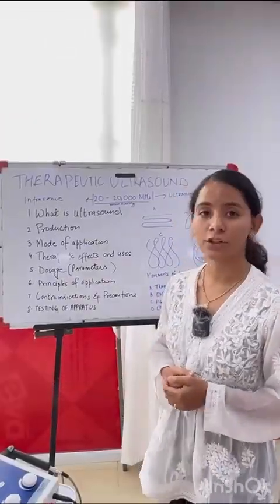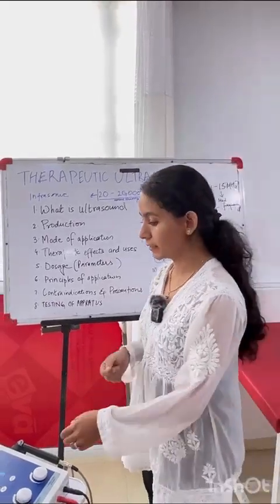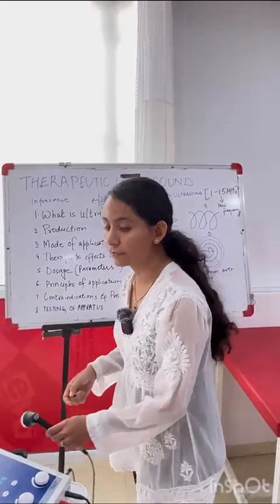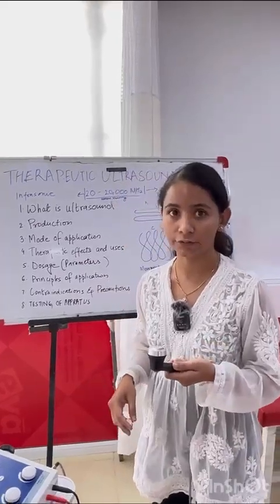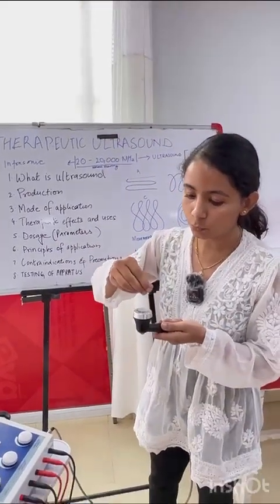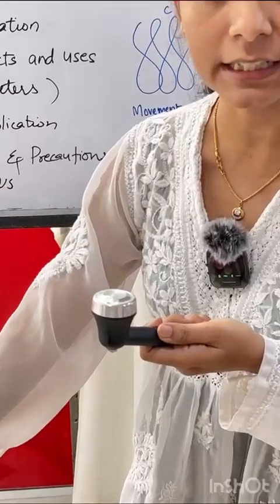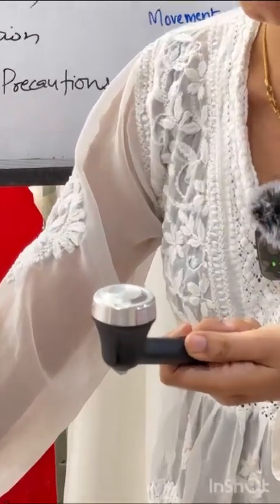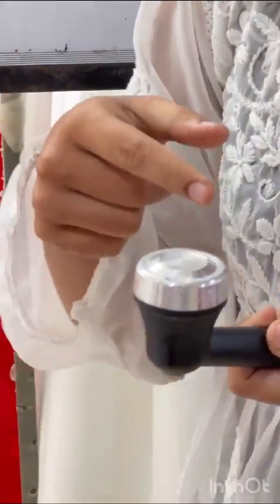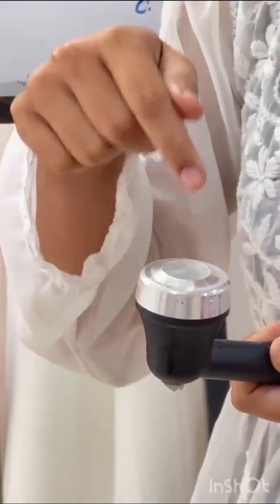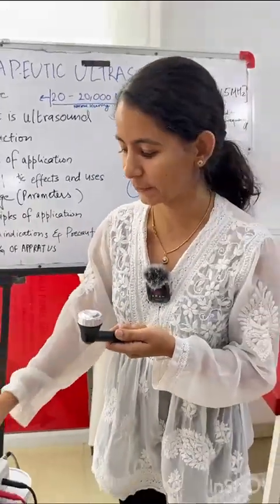Now let's talk about testing of the apparatus. For testing, we set different parameters on the machine, take the head of the ultrasound, put water on the head, and increase the intensity to check for ripple formations on the head of the ultrasound. If ripple formations are present, that means the machine is working.